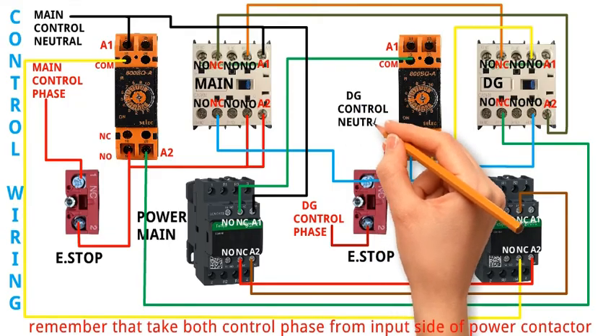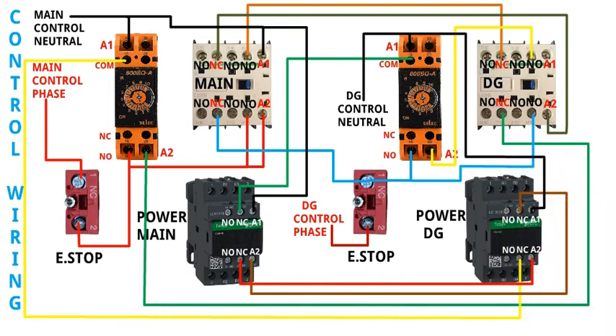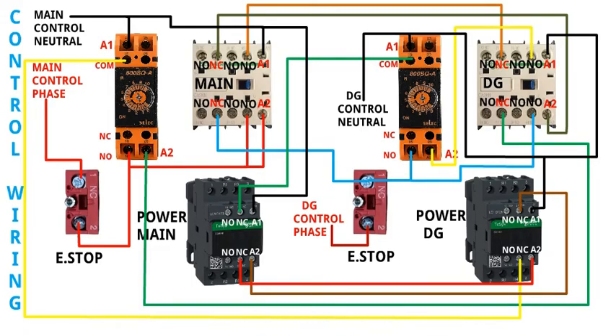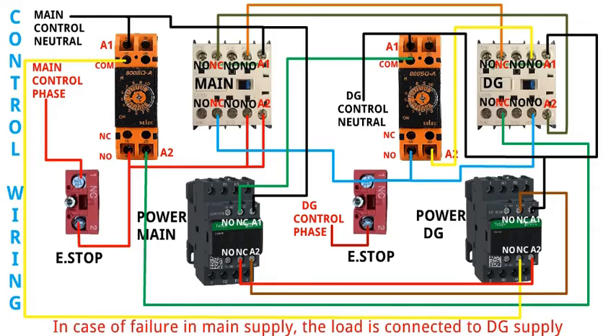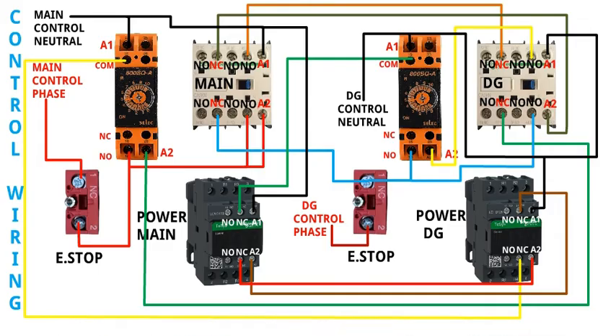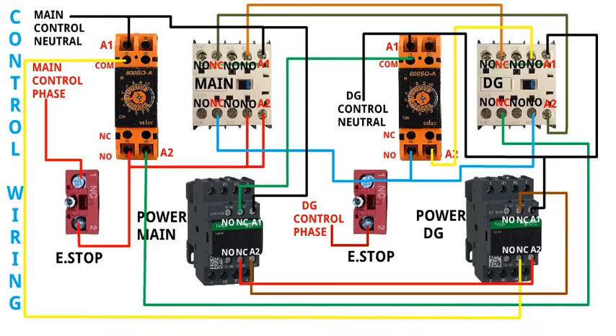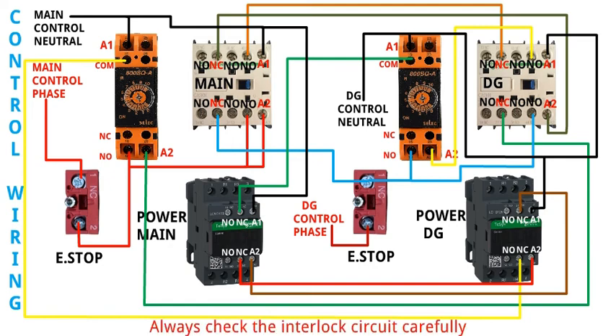Always remember to take both control phases from the input side of the power contactor. Our control wiring is complete. When the main supply is on, the load is connected to main supply. In case of failure of main supply, the load is connected to DG supply. Both on-delay timers are used to create a time gap between changeovers. Always keep both mains and generator supplies separate in the control wiring, and always check the interlock circuit carefully.